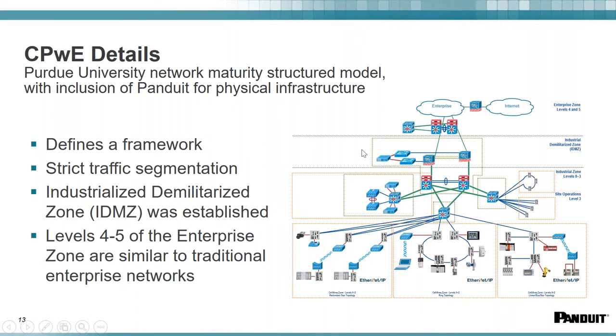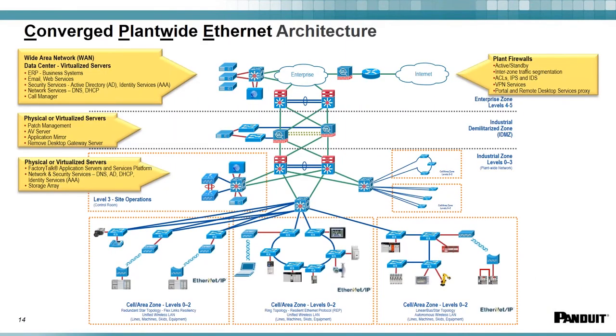This architecture also takes into account something we call DMZ, the demilitarized zone. Between enterprise systems and factory systems, designers always found a good reason to segregate and separate these networks. The way they did it is by adding demilitarized zone devices that basically stop certain traffic from reaching the enterprise layer, either because it's not needed or because it could jam the network at the enterprise. It's simply the way they separate the different architectures. So that's logically how an architecture of a control system is placed within the enterprise communication architecture.